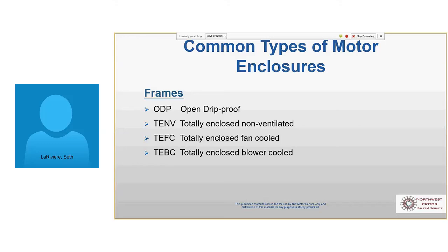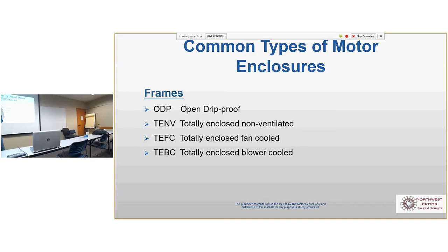And then TEFC is by far the most common enclosure. That's what we've got right here with the fan on the back. And then TEBC is the blower cooled, like the other one I was explaining with the adjustable speed drive motor, where it's got basically a little pony motor that sits on top that has a fan and a blower that blows air into the frame of the motor, or over the frame of the motor.